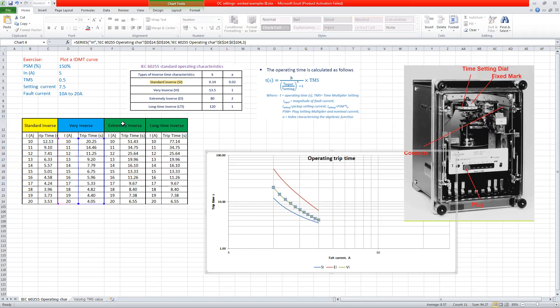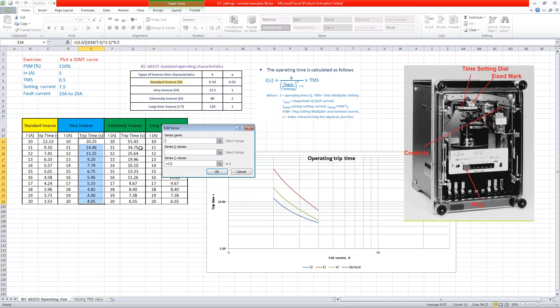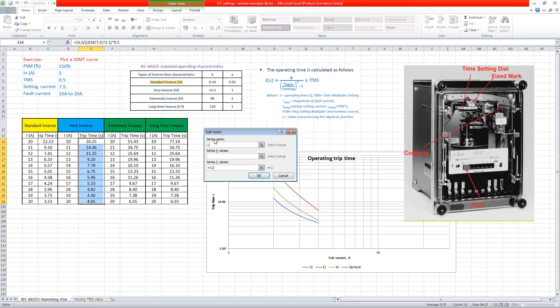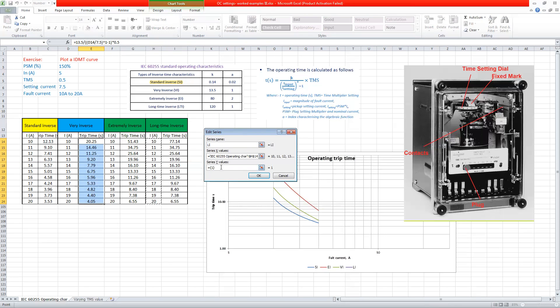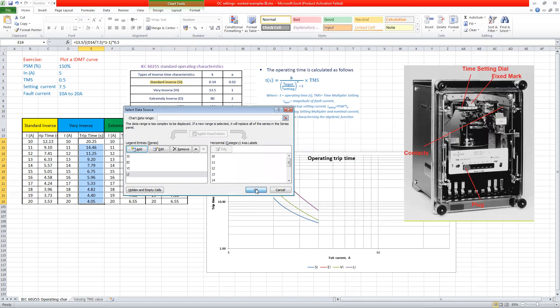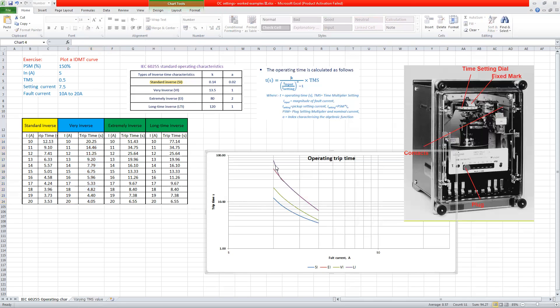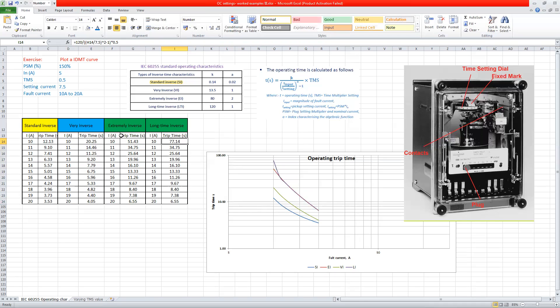And then extremely inverse is this one. And then I think we haven't plotted for the long inverse, but we could do if we want it. So now we can do this way. So now you can see that one is also plotted, which is very similar to the extreme inverse, but at low, there are differences at low currents. So for example, at low current at 10, this is 51, but that one is 77. So for example, at 10, you look at something 77.14, but this one, the extreme inverse at 10 is 51.4 seconds.